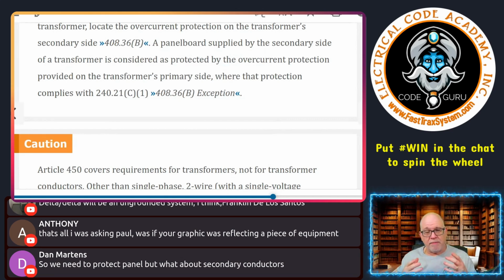So what does that mean? That's the one allowance, for example, where I'm protecting it primary only, okay? And I meet all the rules that said, look, if it's a single voltage, if I'm just doing a 480 to a 240, right? Or a 240 to a 120, single voltage. If I'm doing that, then guess what? Under the exceptions of 408.36(B), that panel board is considered protected based on the primary protection. And we already know that that protects the transformer.